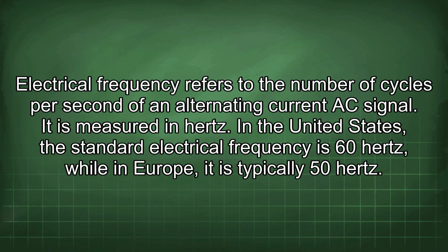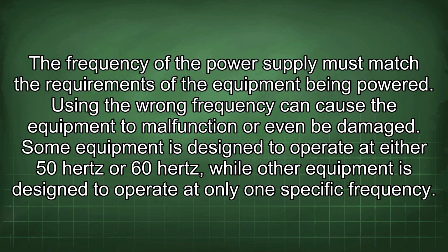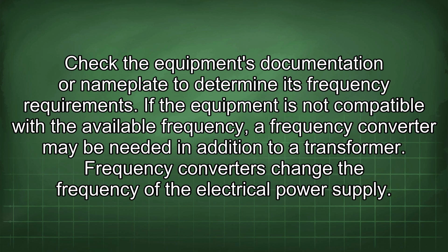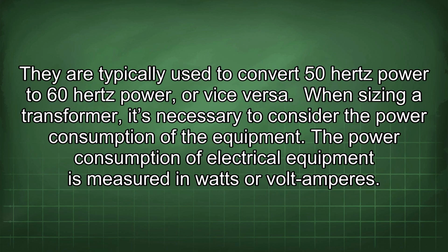In the United States, the standard electrical frequency is 60 Hz, while in Europe, it is typically 50 Hz. The frequency of the power supply must match the requirements of the equipment being powered. Using the wrong frequency can cause the equipment to malfunction or even be damaged. Some equipment is designed to operate at either 50 Hz or 60 Hz, while other equipment is designed to operate at only one specific frequency. Check the equipment's documentation or nameplate to determine its frequency requirements. If the equipment is not compatible with the available frequency, a frequency converter may be needed in addition to a transformer. Frequency converters change the frequency of the electrical power supply. They are typically used to convert 50 Hz power to 60 Hz power, or vice versa.